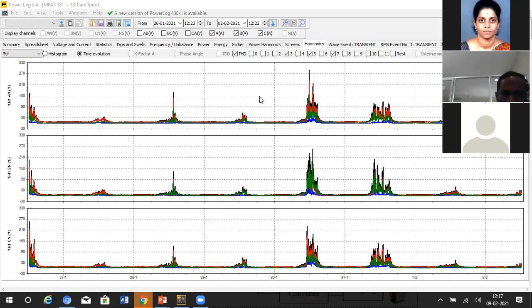So my fundamental current quantity is often less than the distorted quantity, or distorted current. If you split the RMS current into fundamental current and harmonic current, the fundamental current is much less than the harmonic currents. That's why sometimes the THD reaches even beyond 100%.